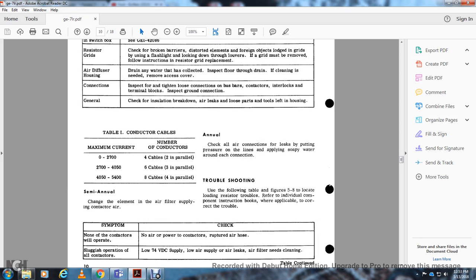Table 1, conductor cables. Maximum current 0 to 2700: number of cables 4, of the conductors, 2 parallel. 2700 to 4050: 6 cables, 3 in parallel. 4050 to 5400 maximum current: 8 cables, 4 in parallel.